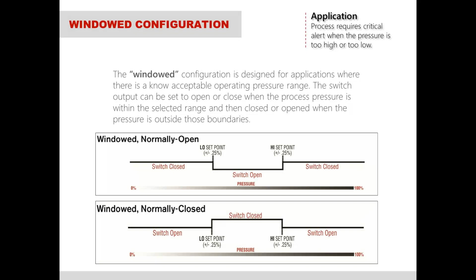What this does is you'll define 2 set points. You'll define a low set point, and then you'll define a high set point. When the pressure is below the low set point, it's closed. When it's above the low set point, but also below the high set point, it's open. So when it's in that window of the set points, the switch is open, and then it's closed when it's outside of the window. And you can set that either vice versa, whether the switch is open in the window or the switch is closed inside of the window.